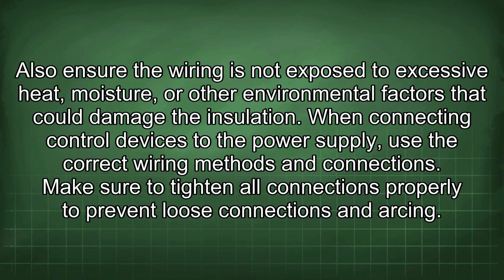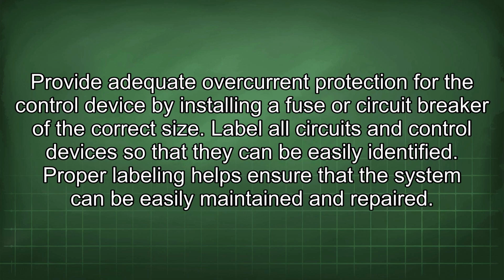When connecting control devices to the power supply, use the correct wiring methods and connections. Make sure to tighten all connections properly to prevent loose connections and arcing. Provide adequate overcurrent protection for the control device by installing a fuse or circuit breaker of the correct size. Label all circuits and control devices so that they can be easily identified. Proper labeling helps ensure that the system can be easily maintained and repaired.